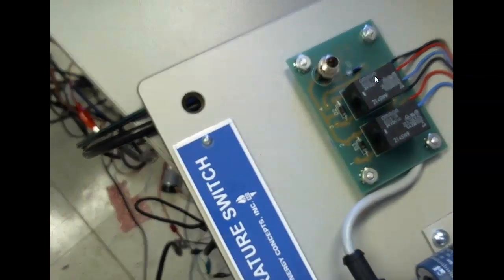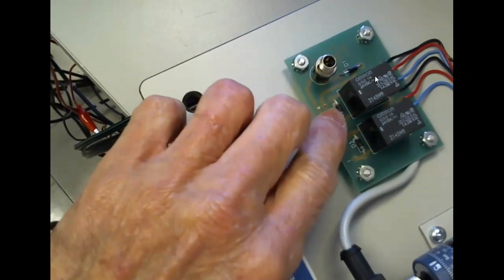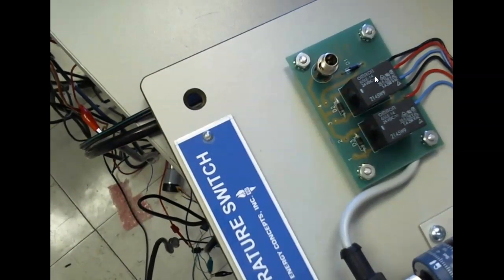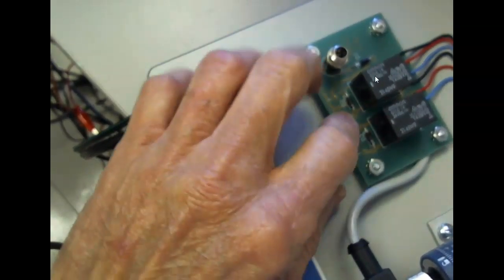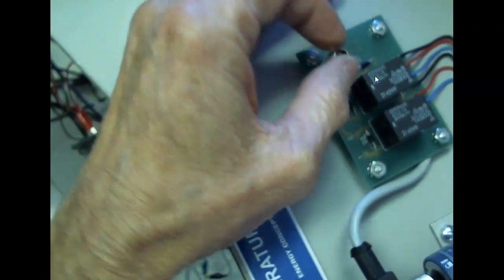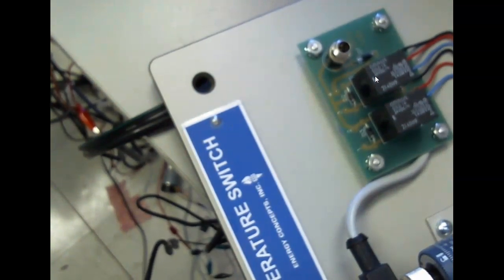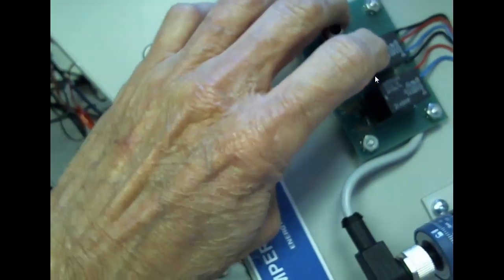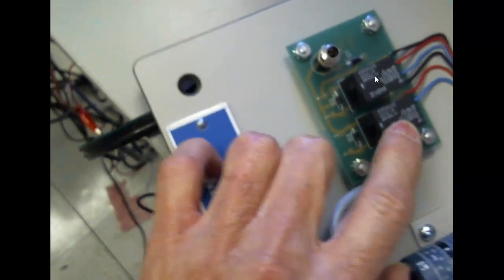What they're doing is bringing this up to two little relays. By the way, these are counter EMF diodes. What happens when we de-energize a coil? It produces a real high voltage output. So these right here are in here to eliminate that counter EMF. This diode is in here in case somehow you get your power supply wired backwards, so you're not going to burn your sensor up. So one of them comes over here. We'll have to figure out the white one comes to this one on this side, and then the black one comes to this one on this side, and then we have terminals down here.